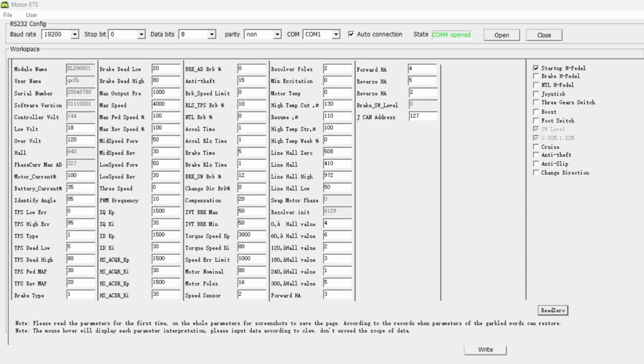Next was the regenerative braking. This will be a bit of trial and error to get right once the bike is going, but for the time being, I added 10% for throttle off and 12% under braking. And finally, I set the max current to 35% because the controller has a 500 amp maximum rating. This should give about 175 amps, which is slightly over the 2C continuous discharge rating of the battery, but still under the 3C burst rating. I'll use this setting for testing and see how the battery performs.